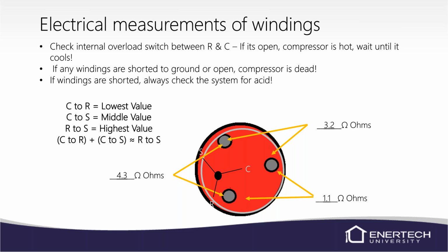If you've got 500 ohms on start to common, then we've got a problem with our compressor. So they should have resistance, but it shouldn't be real high. Obviously, if you get OL, then it's open. So you should have some resistance. It just should not be high.